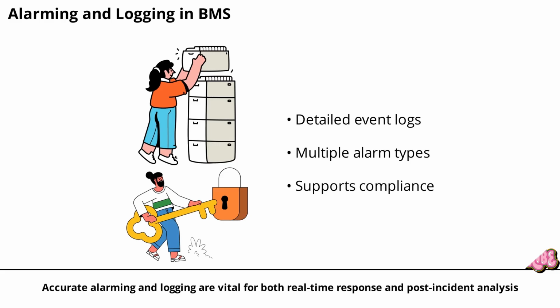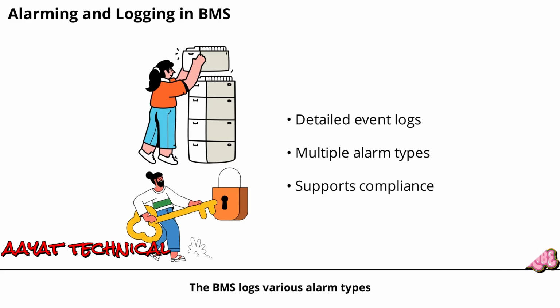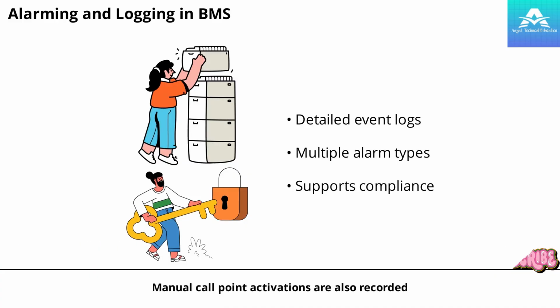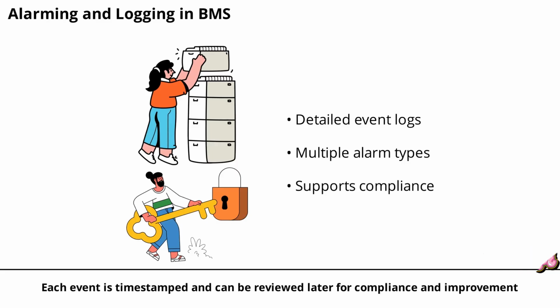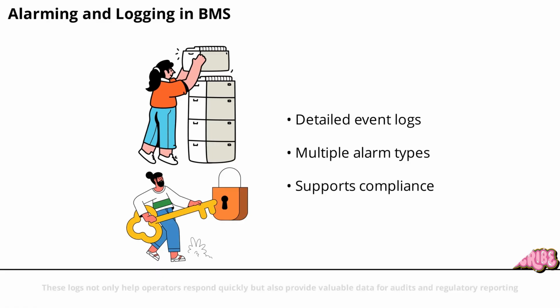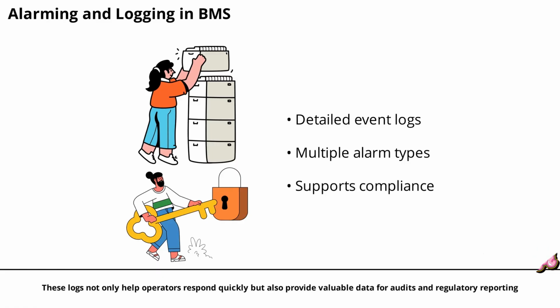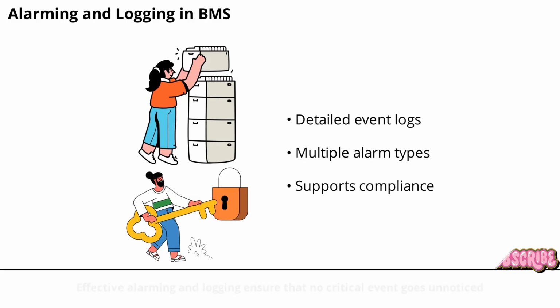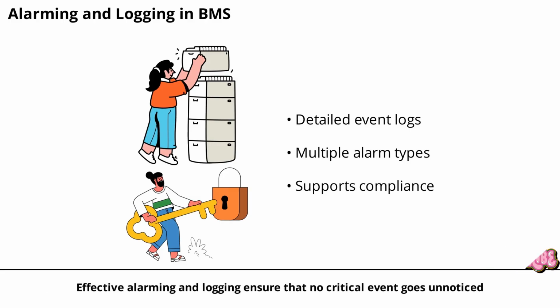Accurate alarming and logging are vital for both real-time response and post-incident analysis. The BMS logs various alarm types, such as fire alarm activation, smoke detection, damper feedback failures, and unsuccessful AHU shutdowns. Manual call point activations are also recorded. Each event is time-stamped and can be reviewed later for compliance and improvement. These logs not only help operators respond quickly, but also provide valuable data for audits and regulatory reporting. Effective alarming and logging ensure that no critical event goes unnoticed.